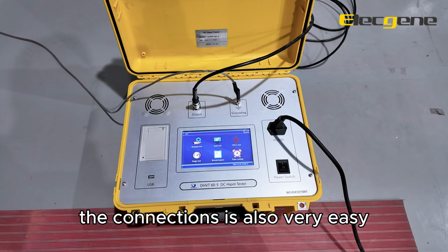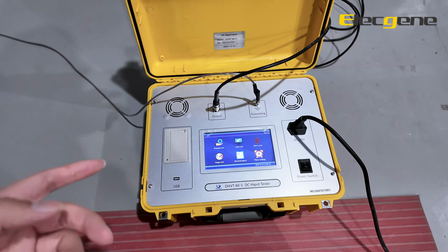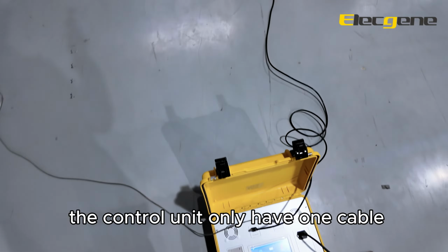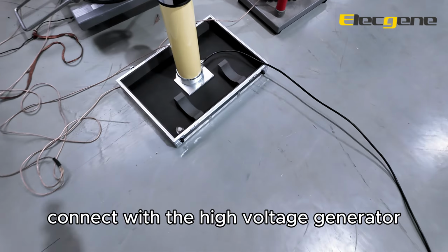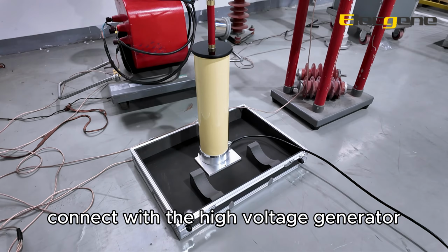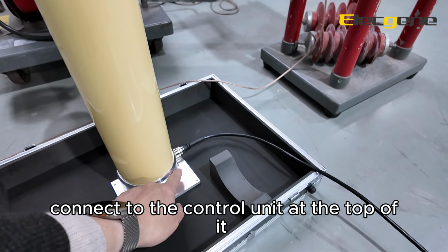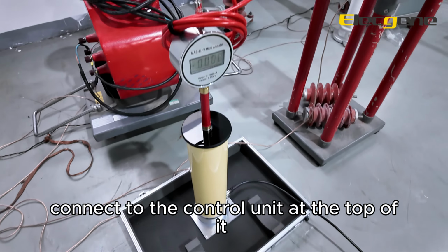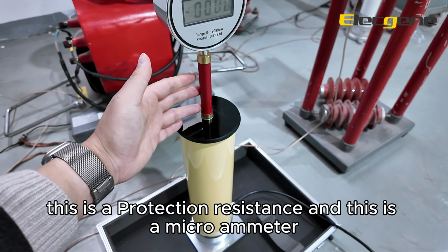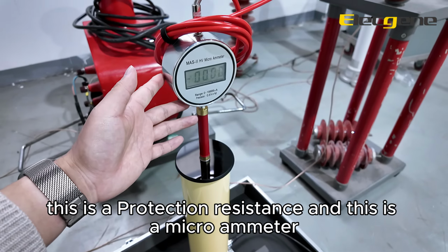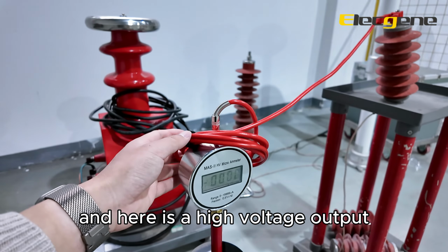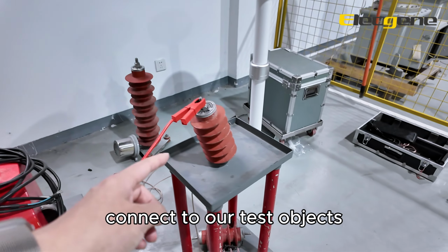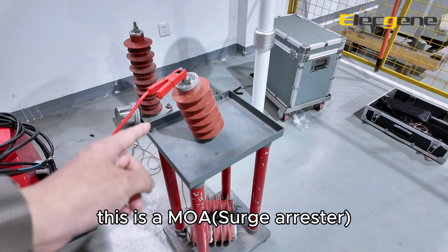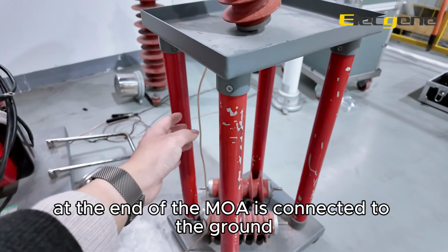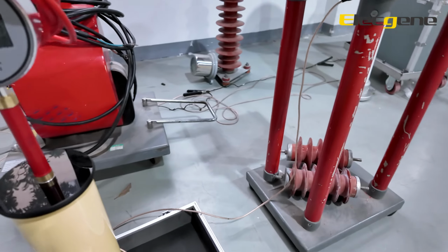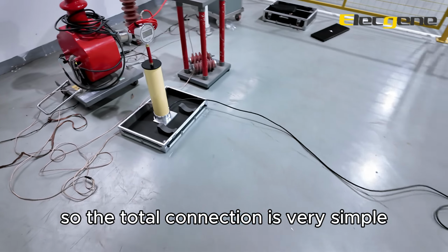The connections are also very easy. So you can see the control unit only has one cable connecting with the high voltage generator, this one. At the bottom, we connect to the control unit. At the top of it, this is a protection resistance, and this is a microammeter. And here is a high voltage output connected to our test objects. And this is a MOA. The end of the MOA is connected to the ground. So the total connection is very simple.